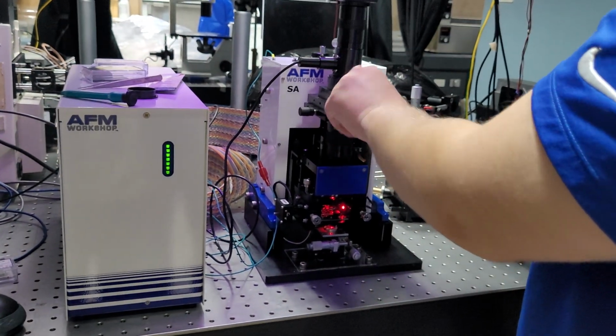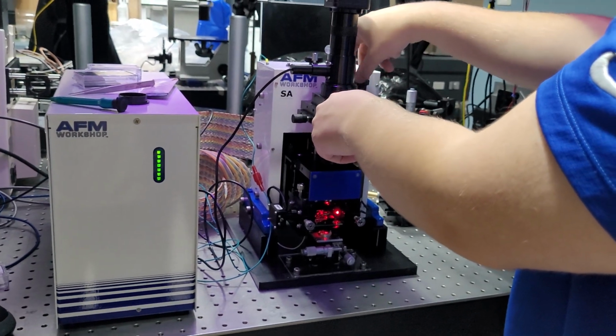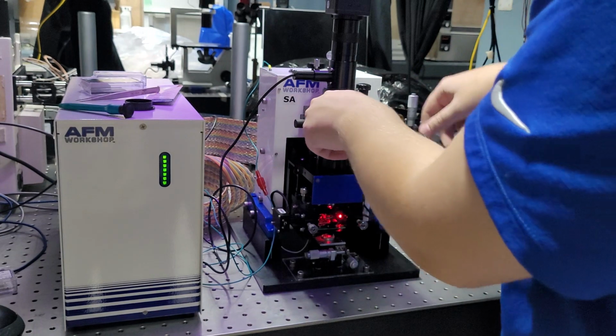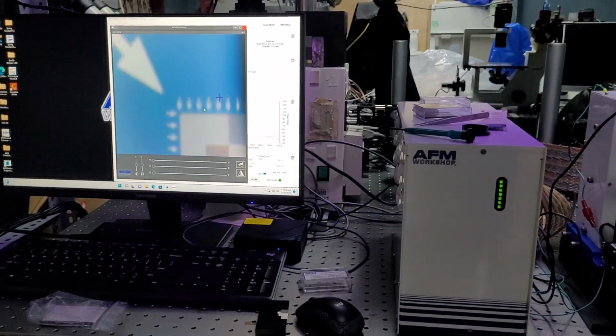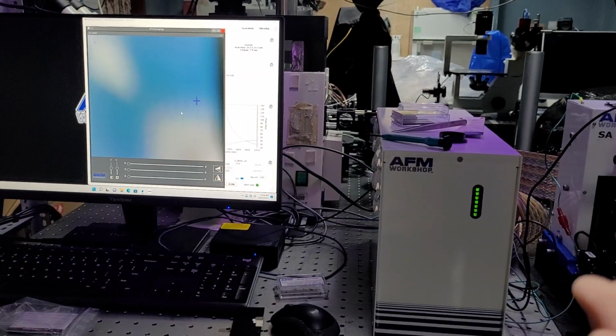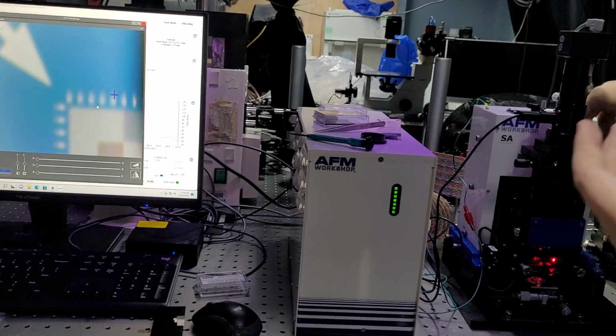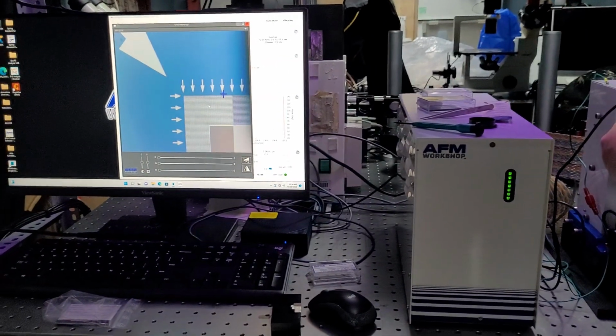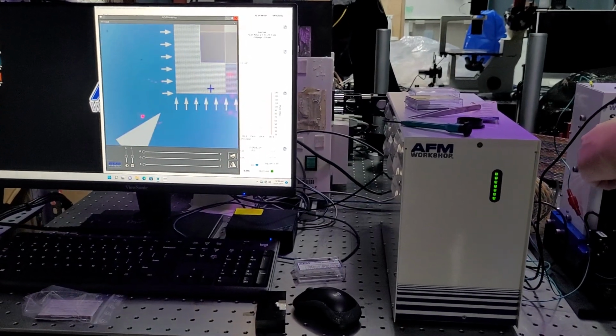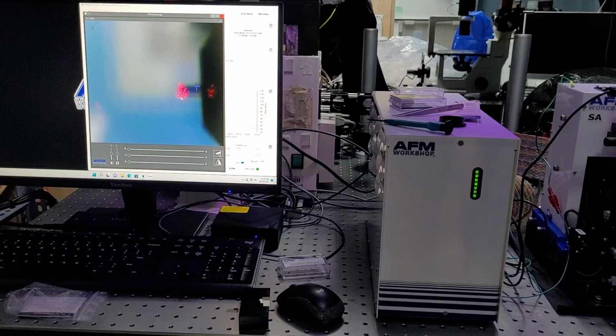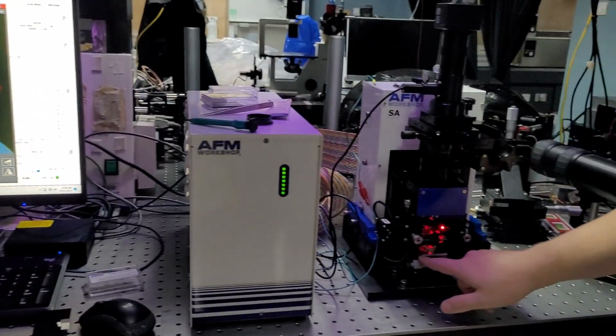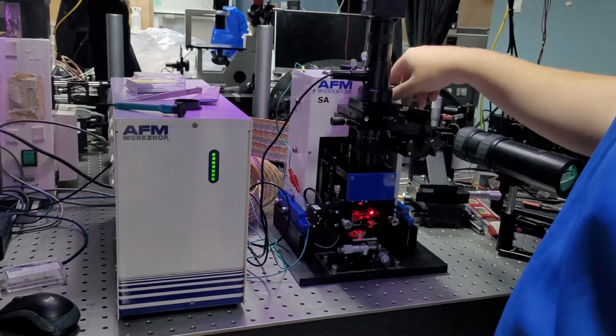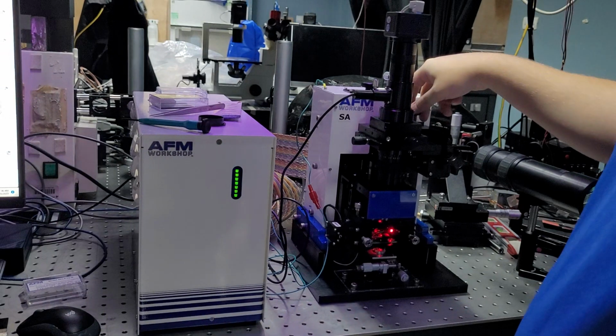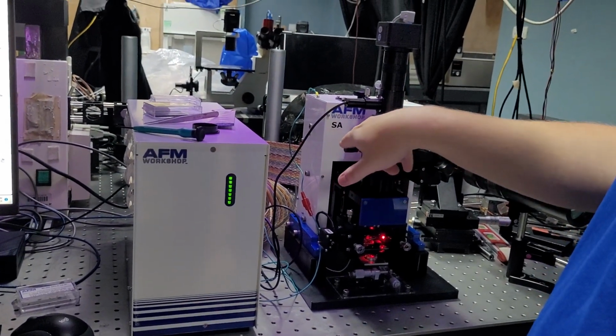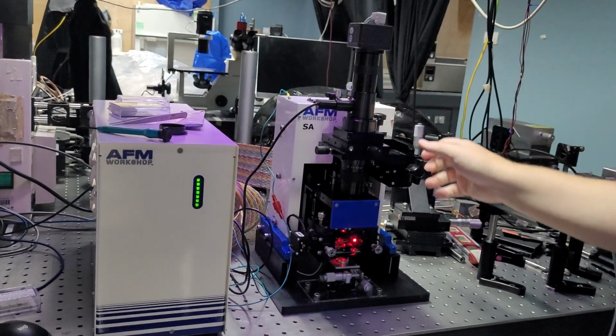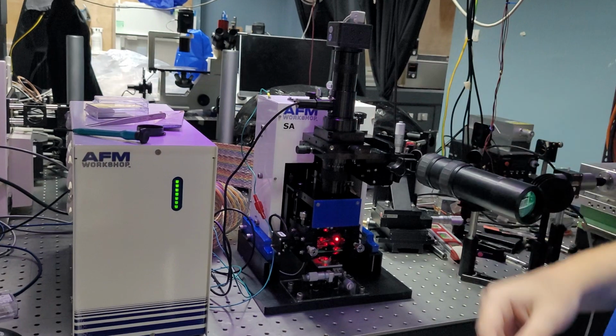Whereas if I, say, want to go up and over here and I want to look at this arrow, now I'm no longer focused on the cantilever. No cantilever. So whenever the cantilever is within the focal length of your camera, you should not need to adjust it. So if you want to look at your sample, use these. Seems very simple, but there have been lots of times where I've had to walk people through how to find it again because they just like to mess with their optics.